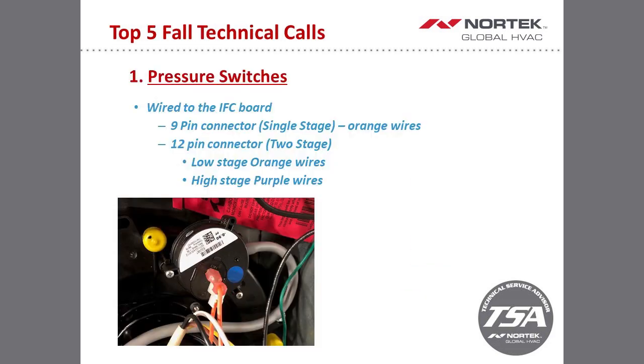Also, the pressure switches are wired into our board at our 9-pin plug for our single stage furnaces. If we have a 2-stage furnace, we'll be working with our 12-pin plug connector. On the single stage side, you will just have orange wires to designate your pressure switch circuit. On the 2-stage, you will have basically two sets of wires. Your orange will be your low fire, and your purple or violet wires will be your high fire switches. On the 2-stage side, you will have a total of four pressure switches, two on your condensate and two on your vent side, but they will be labeled with those color wires to determine what is your high and what is your low. Again, those wires will go back to your main plug, whether that's your 12-pin plug on your 2-stage equipment or your 9-pin plug on your single-stage equipment.